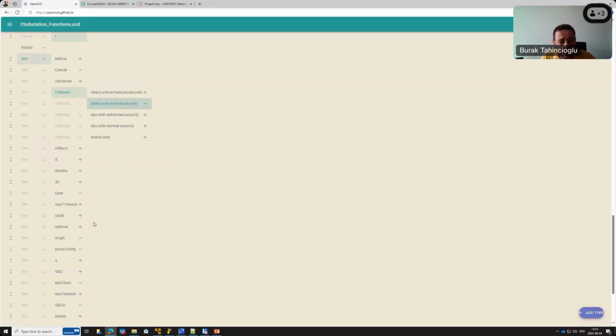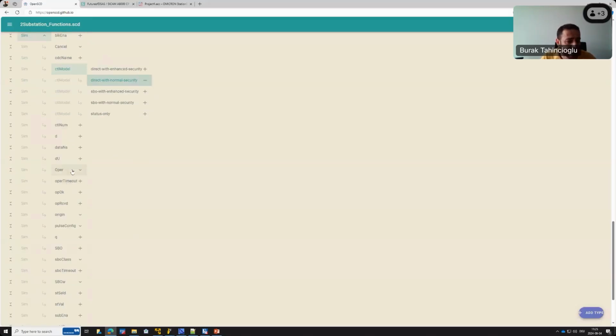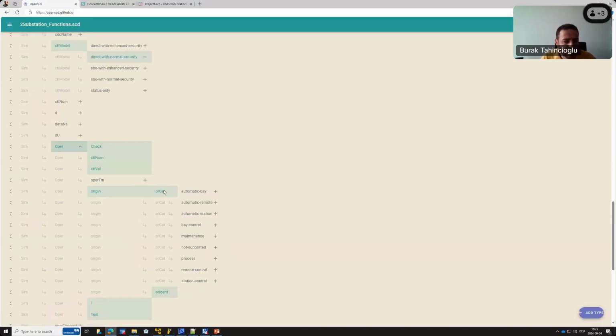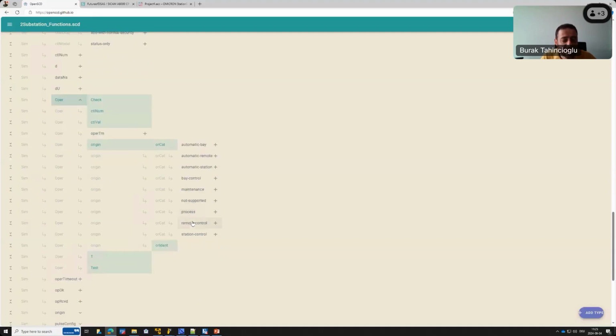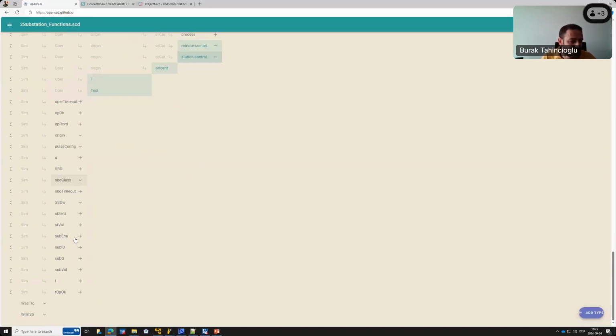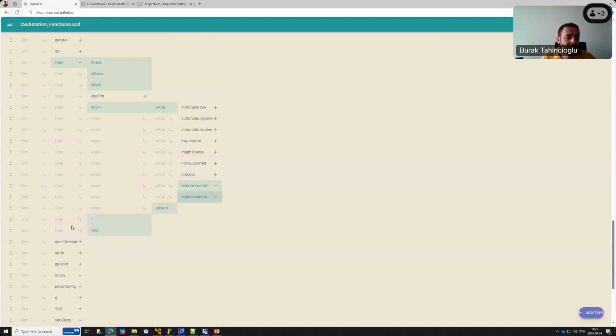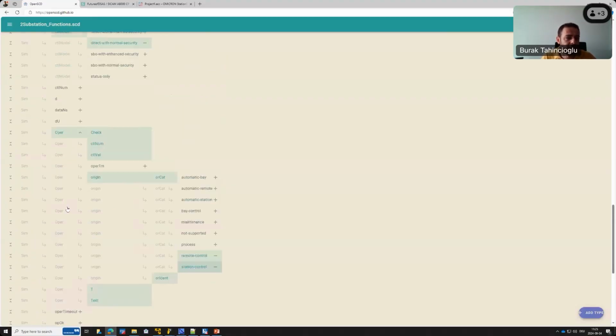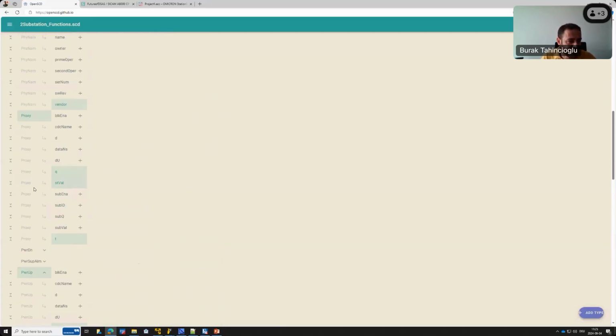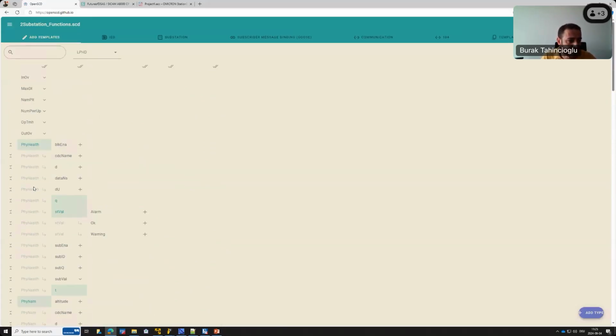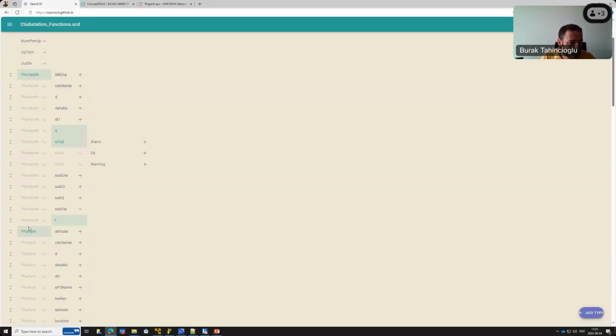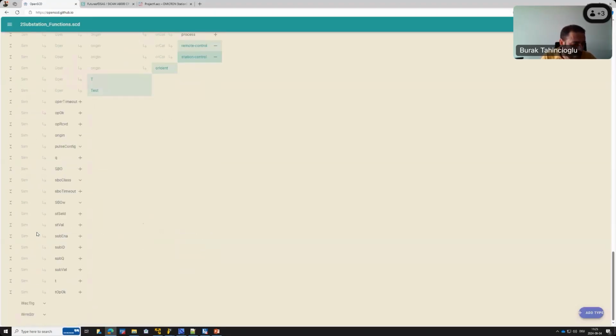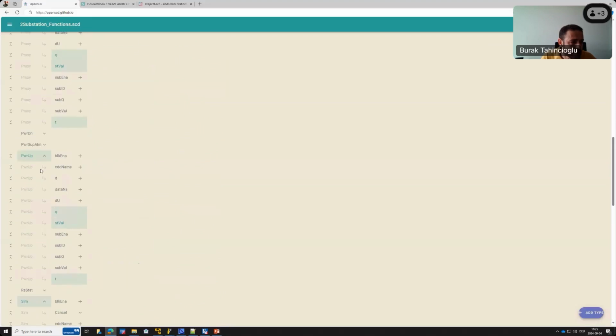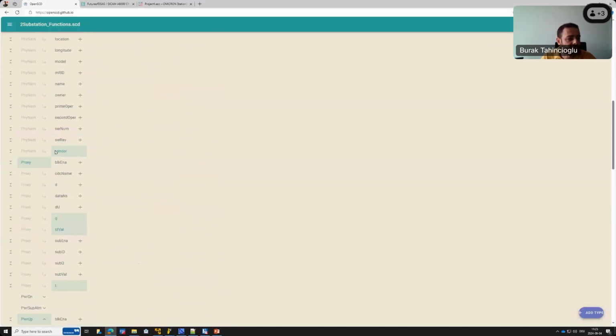But there are other flavors too — Oper, the select-for-operate timeout, and under Oper you also have the originating category, so this controllable object can be controlled by remote or station, among other possibilities we need to add. That was the example for LPHD, which also includes physical health and physical name, the nameplate information. One thing we must also have is PwrUp, Proxy, and the vendor name.